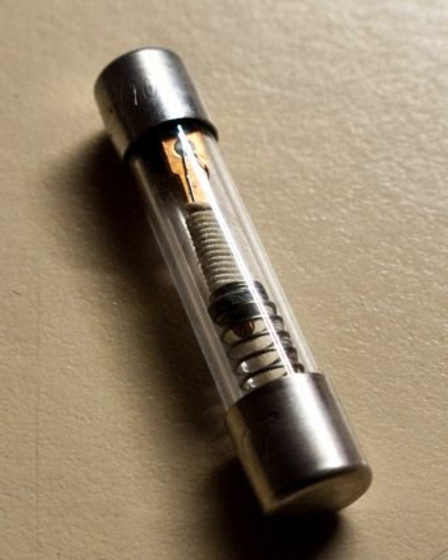Some companies manufacture resettable miniature thermal circuit breakers, which screw into a fuse socket. Some installations use these Edison base circuit breakers. However, any such breaker sold today does have one flaw. It may be installed in a circuit breaker box with a door. If so, if the door is closed, the door may hold down the breaker's reset button. While in this state, the breaker is effectively useless. It does not provide any overcurrent protection. In the 1950s, fuses in new residential or industrial construction for branch circuit protection were superseded by low-voltage circuit breakers.